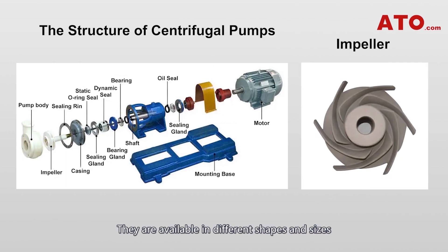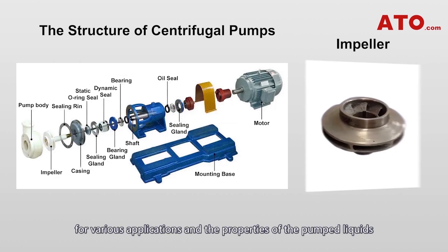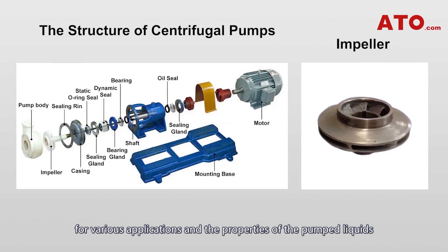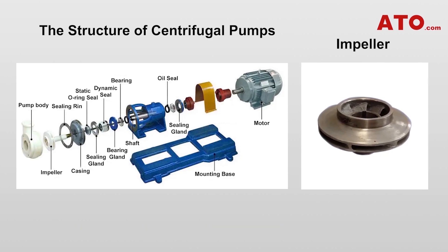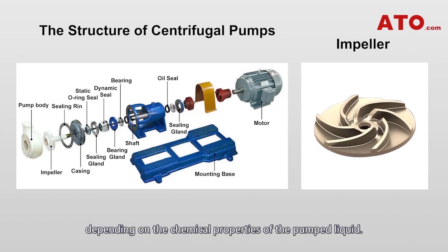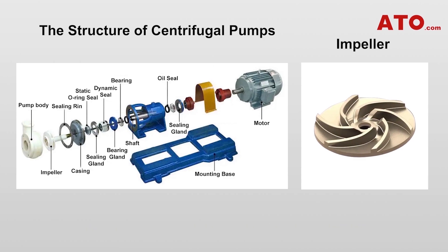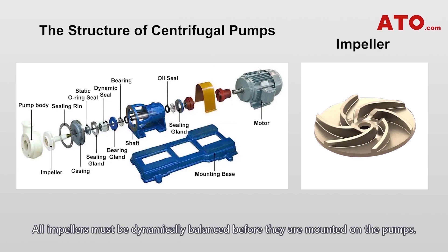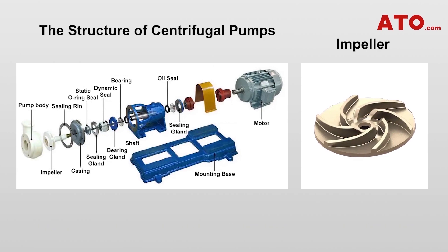Impellers are available in different shapes and sizes for various applications and properties of the pump liquid, and they are composed of a set of backward curved blades. They can be made of a range of materials depending on the chemical properties of the pump liquid. All impellers must be dynamically balanced before they are mounted on the pumps.